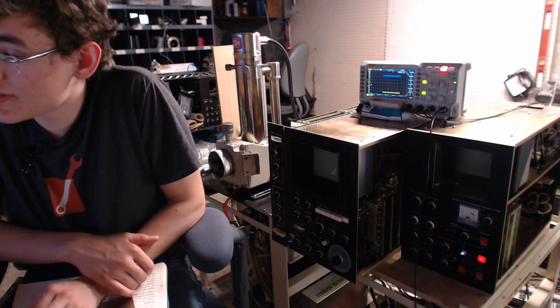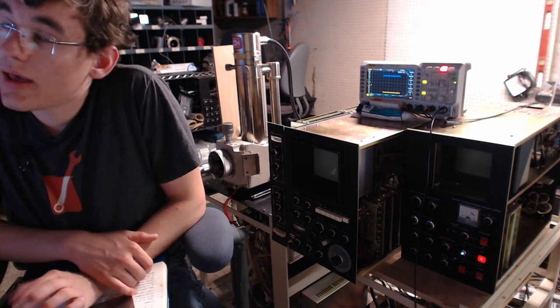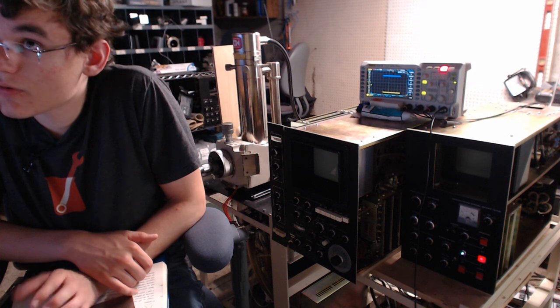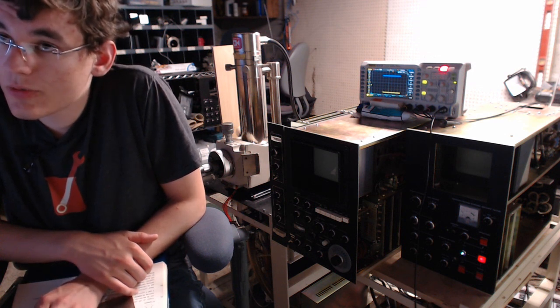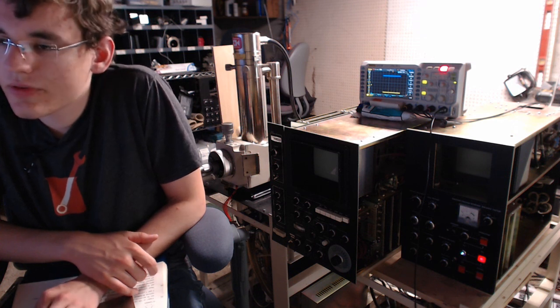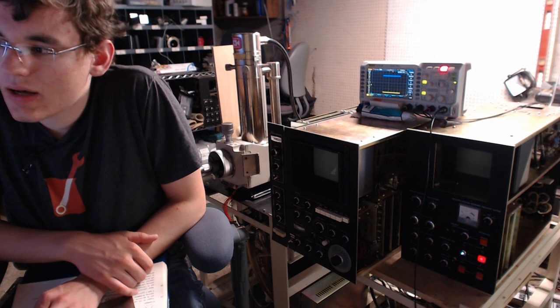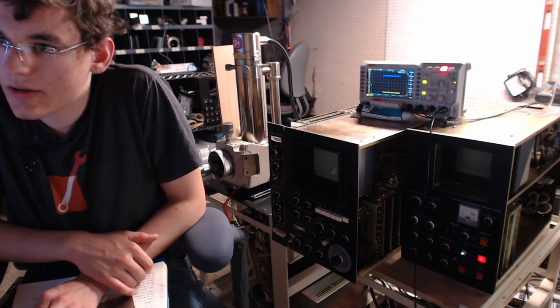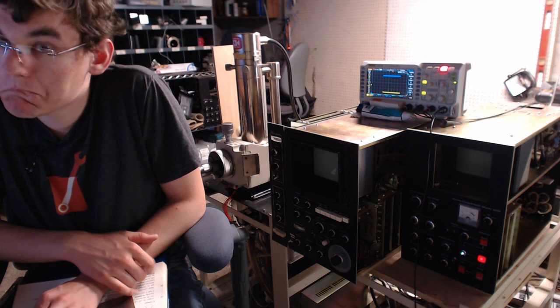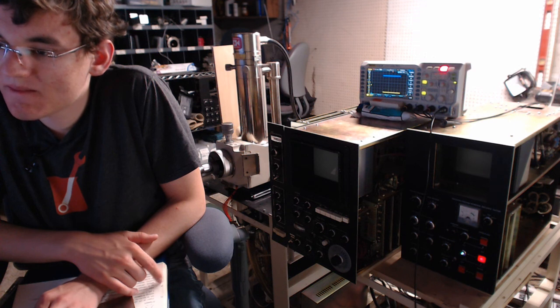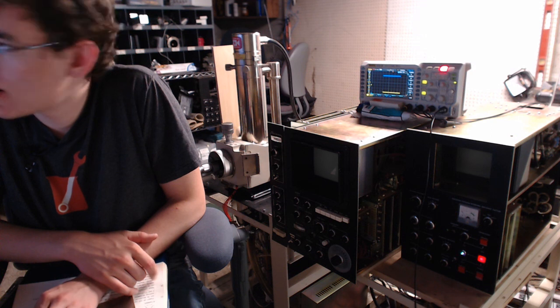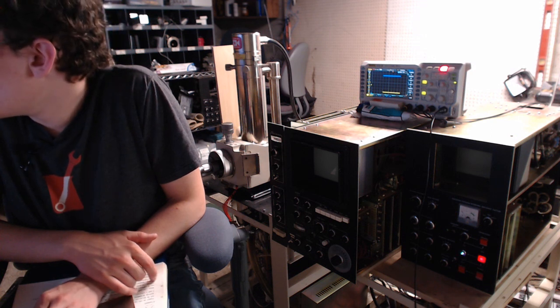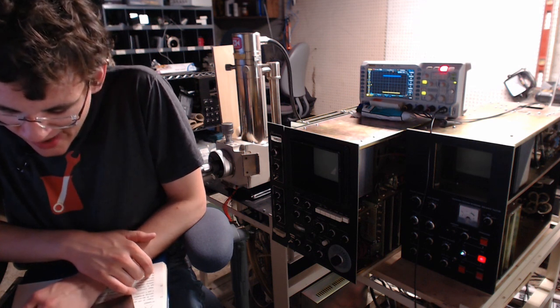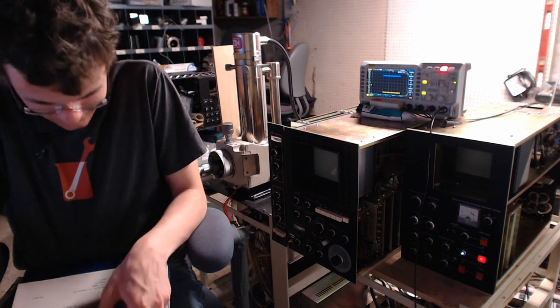Okay, so we're moving in a good direction now at least. So I've ruled out the photomultiplier, and we're back onto the scintillator. And the scintillator could itself just be wearing out over time. I mean, it's old. I've accidentally run it in the atmosphere before. It could have got dust on it. It could have been burned in. There's any number of things that could have happened to the scintillator, and I think I have a spare scintillator already set up. Yeah, I've got a spare scintillator already inside. Okay, so it's not contrast control.